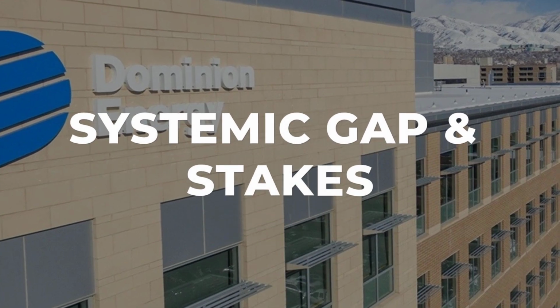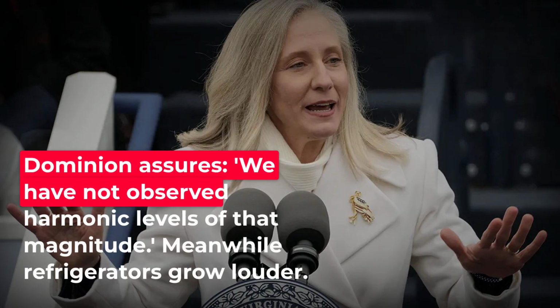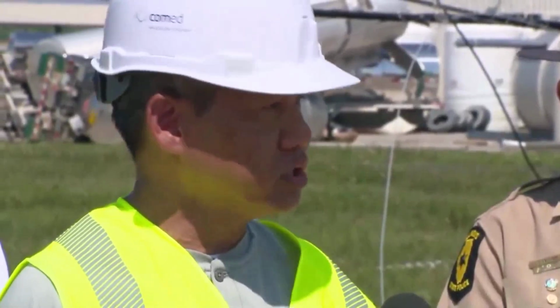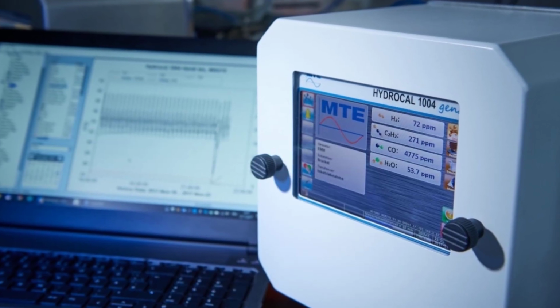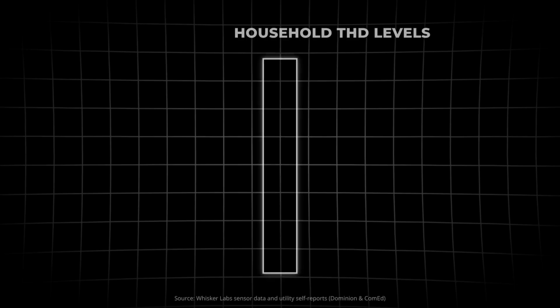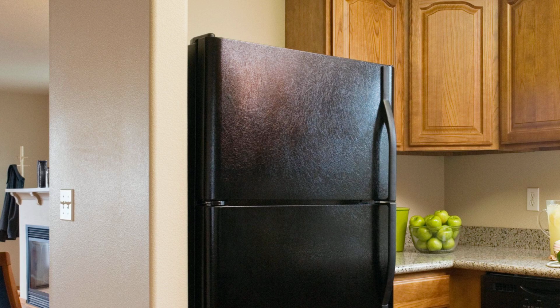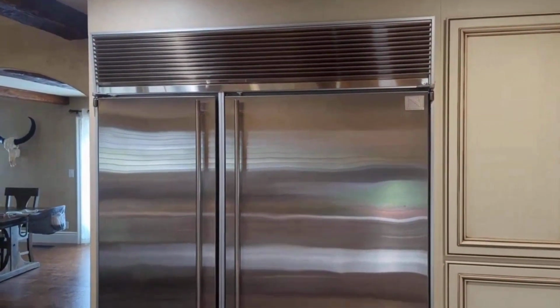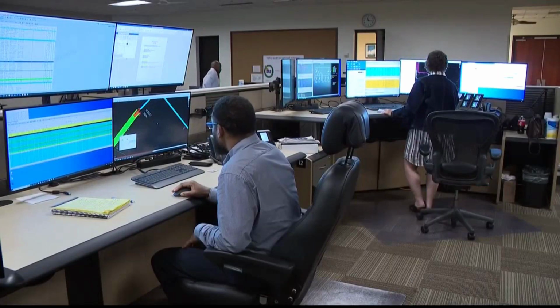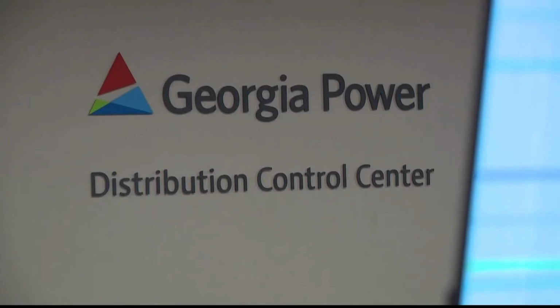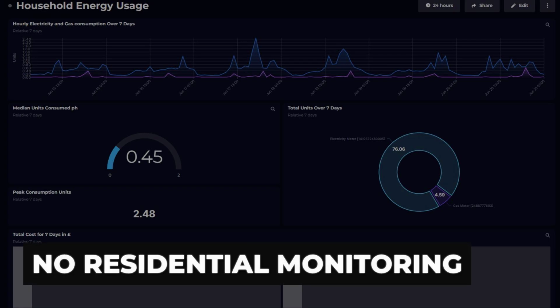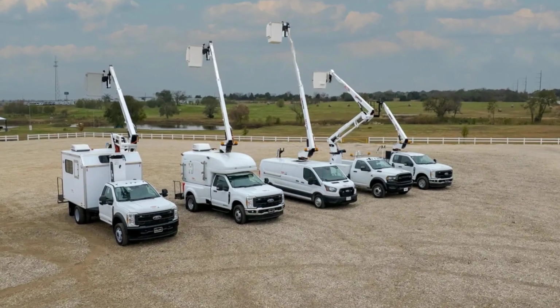Dominion Energy's official line is simple. We have not observed harmonic levels of the magnitude reported. Commonwealth Edison echoes the same doubt, calling the Ting sensor network uncalibrated and insisting their own readings show compliance with the IEEE's 8% limit. For families listening to their appliances struggle and overheat, these denials feel like gaslighting. Utilities monitor the grid from a distance, at the substation, not inside the home, leaving a blind spot where dirty electricity slips through, unchecked and unacknowledged. There is no requirement to log residential power quality, and most utilities have no plans to start.